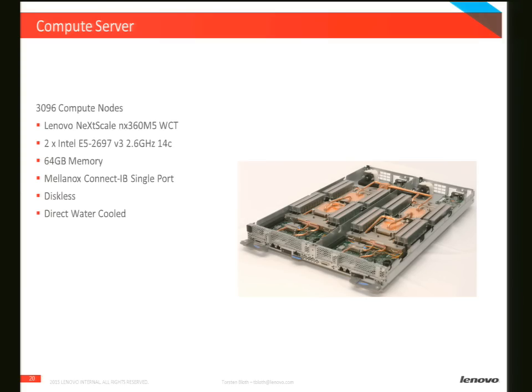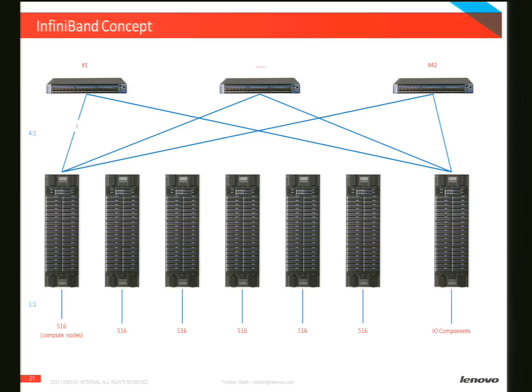So that is absolutely in spec of such an InfiniBand ASIC or the chip itself. I think Mellanox and LRZ is up to 103 degrees on the chip level. So even with 40 degrees temperature on the water side, the chip is not getting hotter than, I think, 80 degrees. So we're absolutely in spec even with 40 degrees. So that's what I mentioned in the former slides. That's the InfiniBand design of the system.